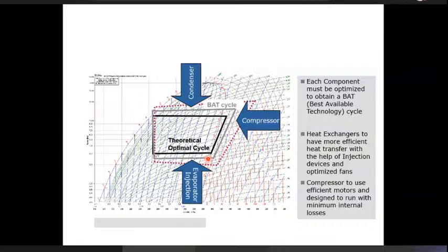Again, an opportunity for moving closer to the theoretical optimal cycle. What do we do on the condenser? What we said here applies to the condenser. Here again, we need to do circuiting. We need to divide the refrigerant into different paths such that the heat rejected is similar, and instead of targeting comparable superheat at the outlet, we look at targeting comparable subcooling. This process requires better control in terms of regulating the refrigerant flow in response to the changing scenario. But right now, if you're looking at steady state condition, we would size the expansion device such that it is closely matching the pressure drop that is required here.